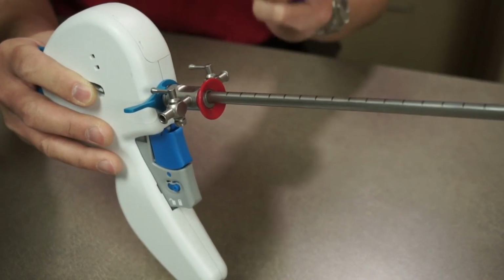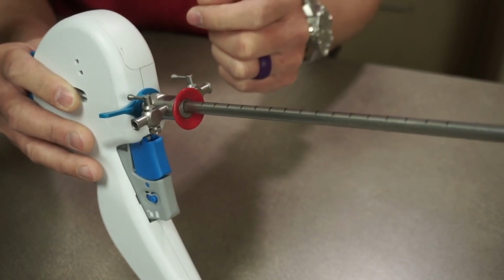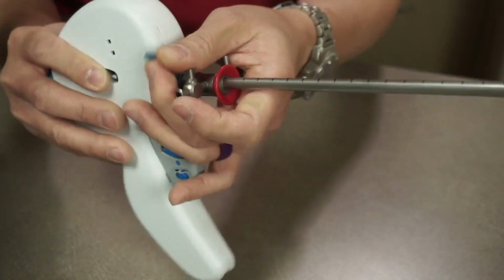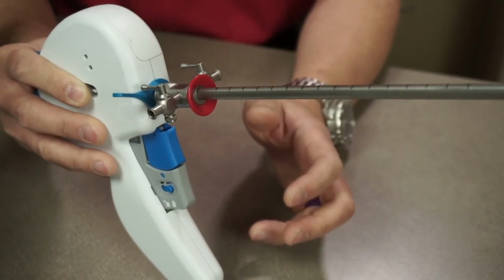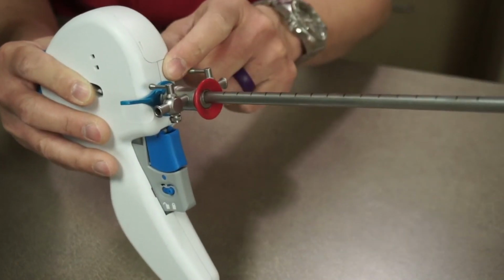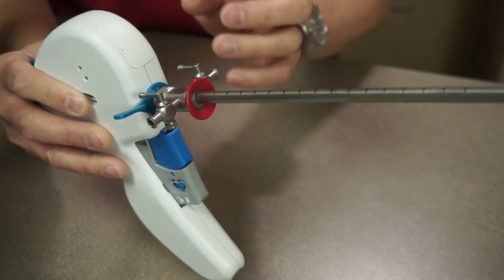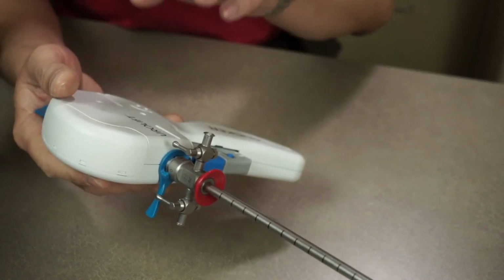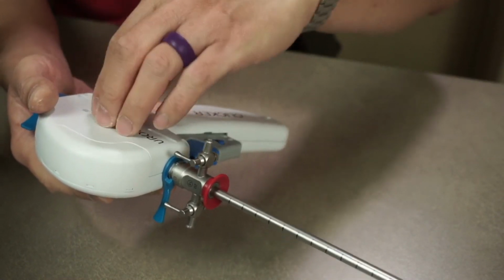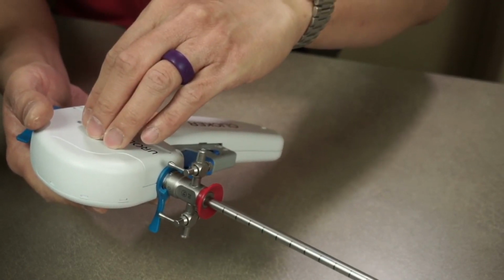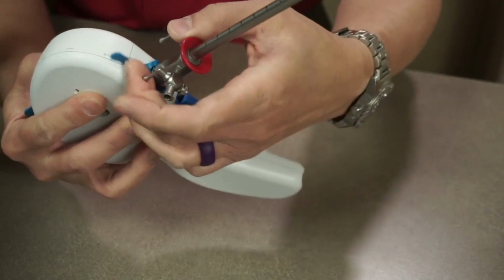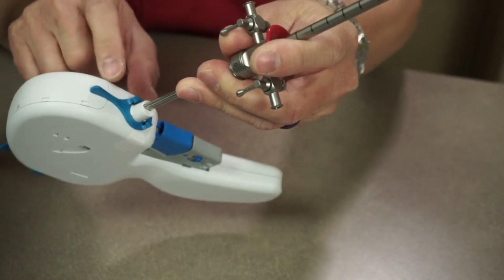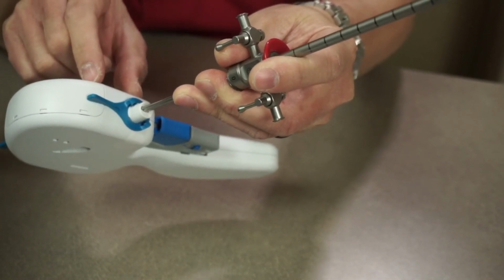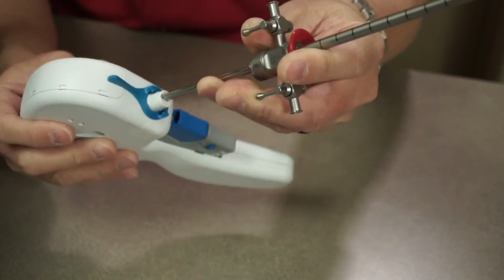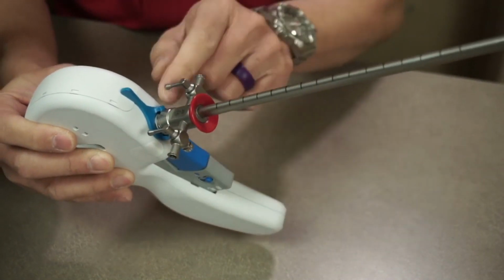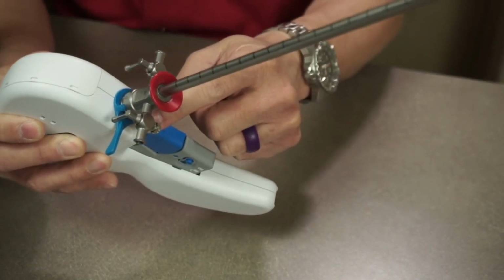I actually handled the upgraded version. I call it UL 2.1. This is much easier on the UL 2.1. So they fixed this problem right here. The second problem is a bigger problem. Because the implant is now a cartridge that mates with the UL2 handle, that interface has a little crack right here because the implant is mating into the handle. So that interface, that little crack, and then the mating of the sheath into this interface causes fluid leak.